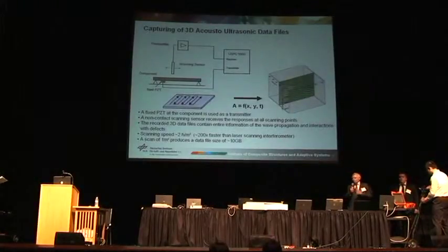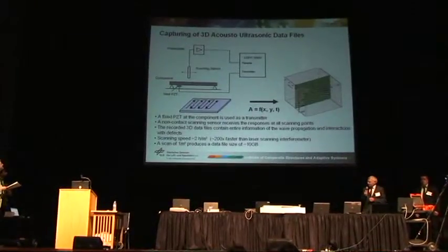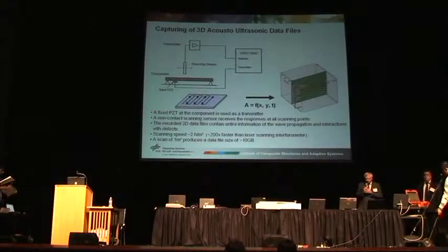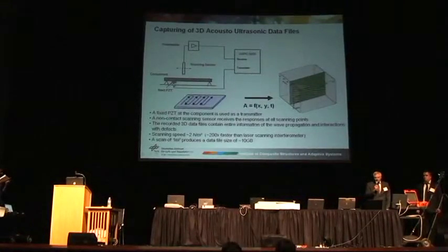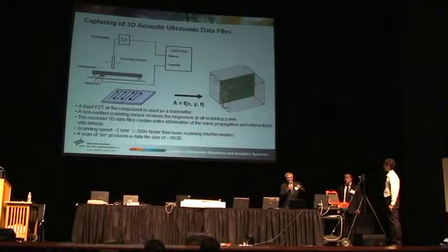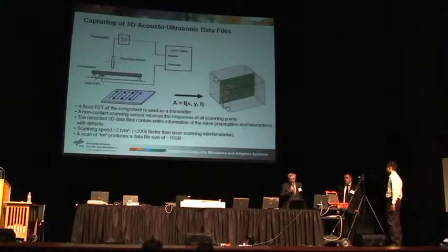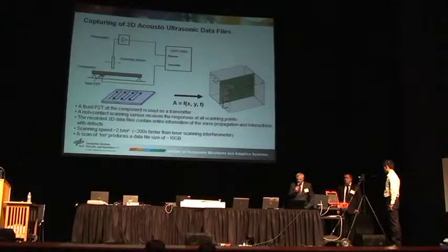It is well known that wave propagation in carbon fiber composites is very complex, as is its interaction with defects. Therefore, it is useful to visualize the wave propagation and its interaction. For this, we used a fixed PZT on the component as a sender, and on the other side, we used an air-coupled scanning sensor. We scan the whole component and are 200 times faster than using a laser scanning interferometer.